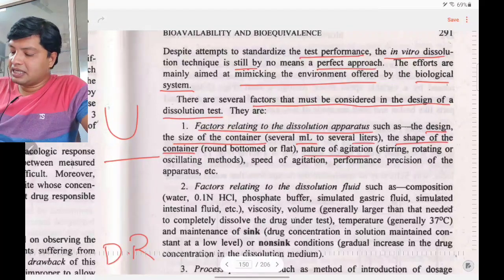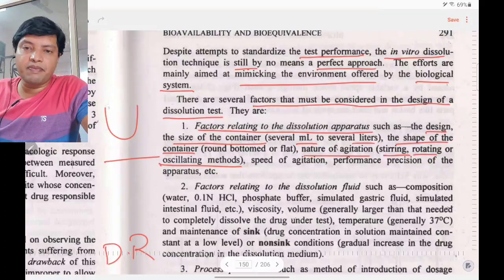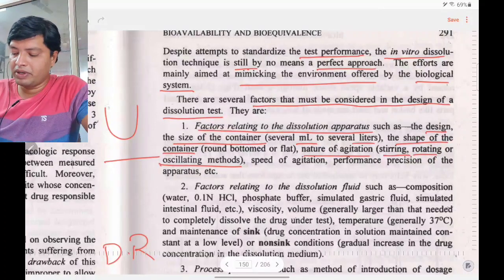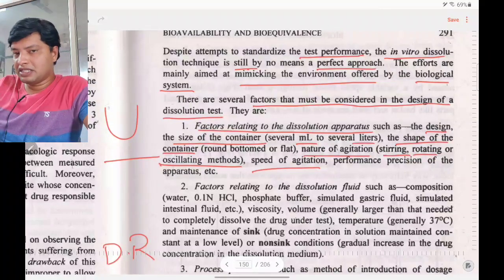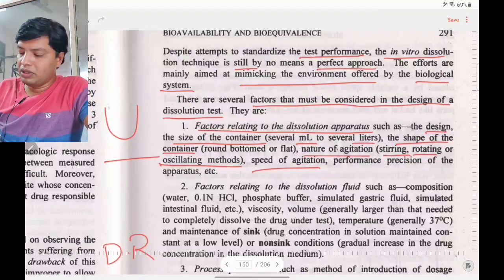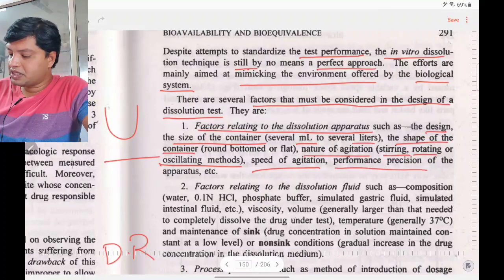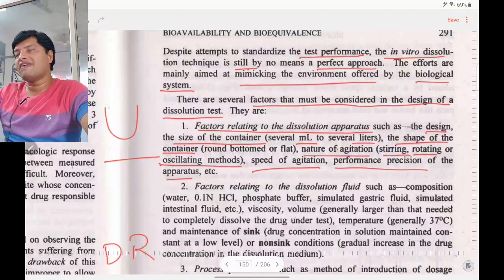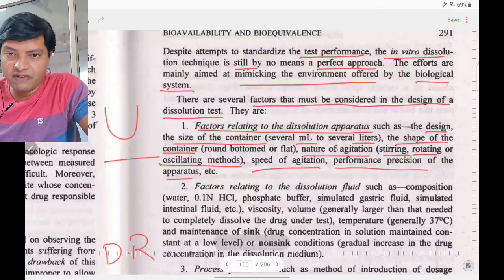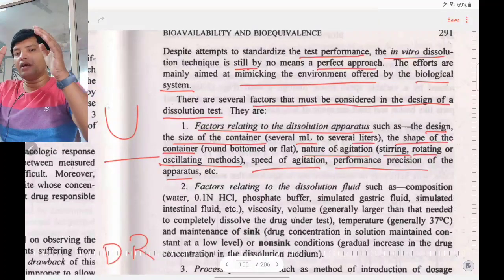The nature of agitation — stirring, rotating, or oscillating methods — and the speed of agitation, as well as the performance and precision of the apparatus. These are the apparatus-related factors that affect dissolution test design.